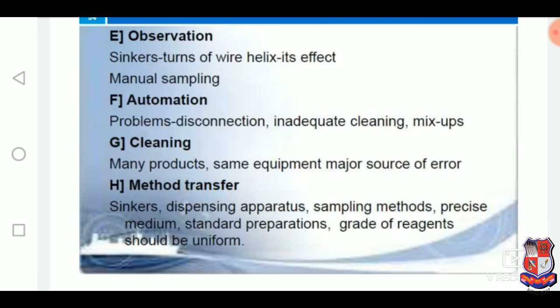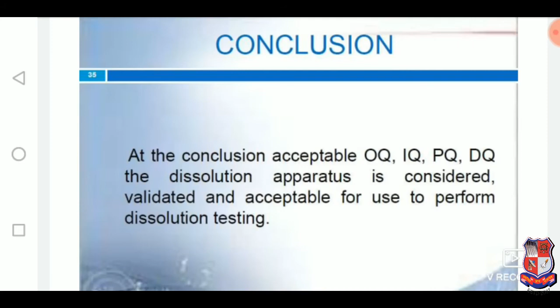So, in conclusion, with acceptable operation qualification, installation qualification, performance and design qualification, the dissolution apparatus is considered validated and acceptable for use to perform dissolution testing. So acceptable operation qualification, installation qualification, performance qualification, and design qualification should be used for that instrument.